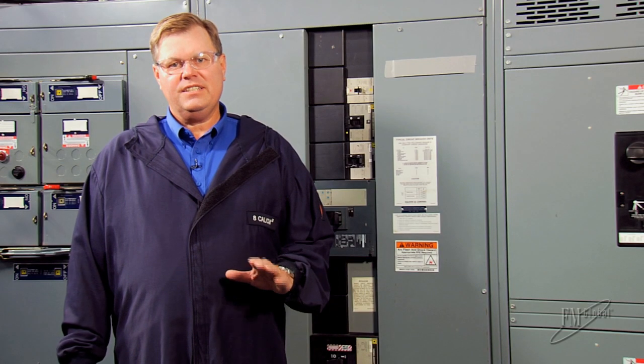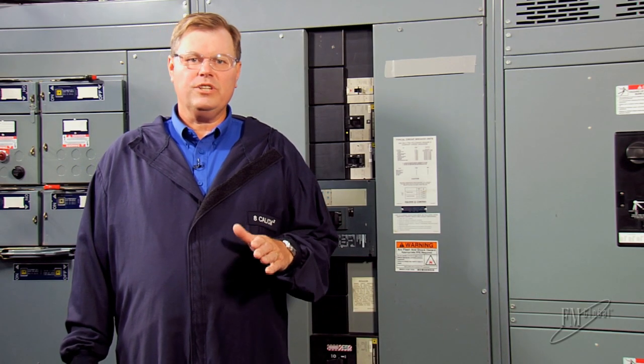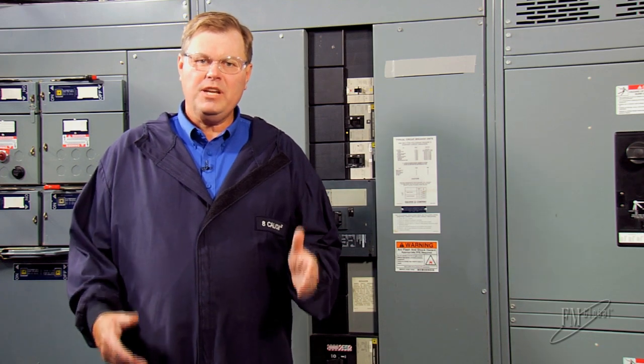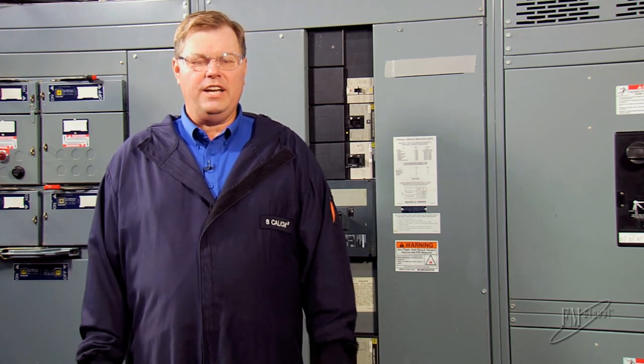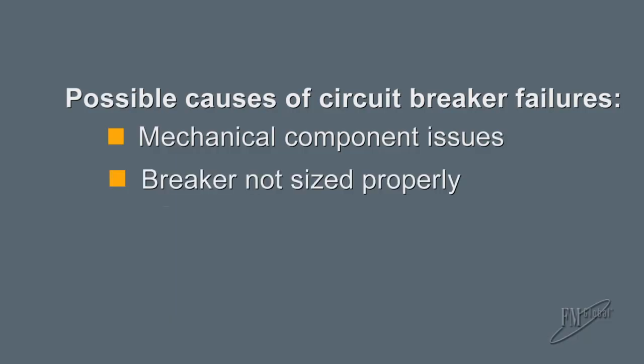This can cause extended current flow and the risk of breaker meltdown, sometimes known as arc flash. If the breaker is not sized properly, it may not be able to clear a fault should one occur. The breaker must be sized for the largest expected fault current.